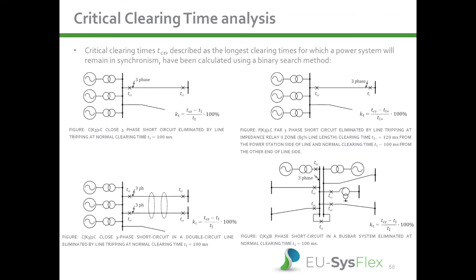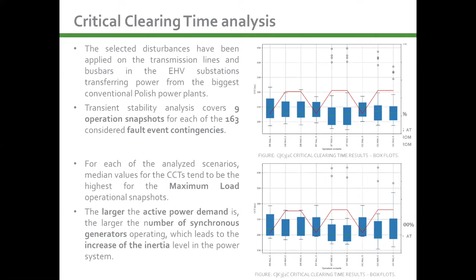Selected disturbances have been applied on the transmission lines and busbars in the Polish transmission network substations, which transfer power from the biggest conventional Polish power plants. For each of the presented disturbance events analyzed, required values of critical clearing times and transient stability margins have been met with sufficient excess. For each of the analyzed scenarios, median values of critical clearing time tend to be the highest for the maximum load operational snapshots. The larger the active power demand is, the larger the number of synchronous generators operating is, which leads to the increase of the inertia level in the power system. An increase in the level of inertia augments the power system transient stability margin.